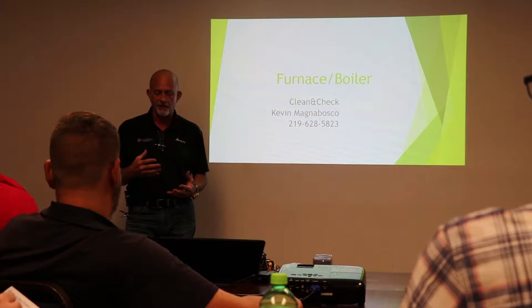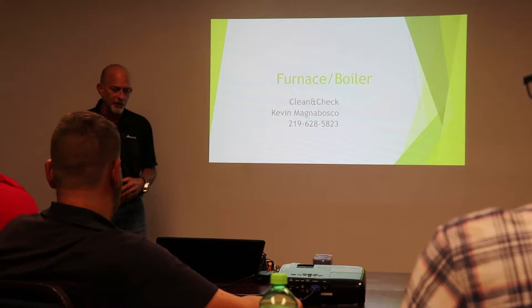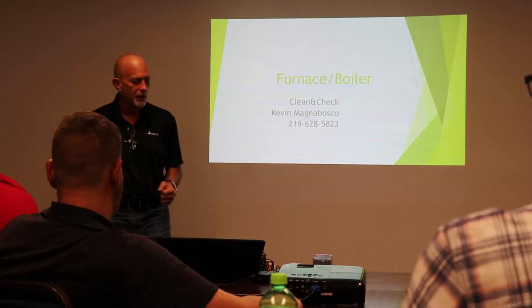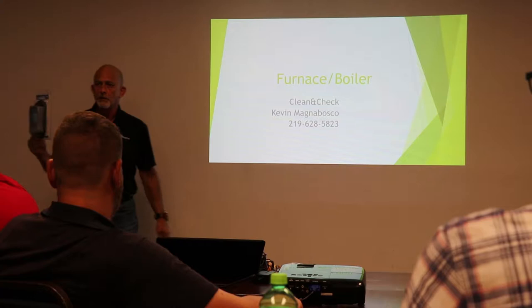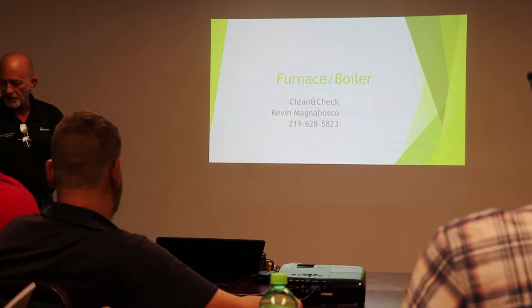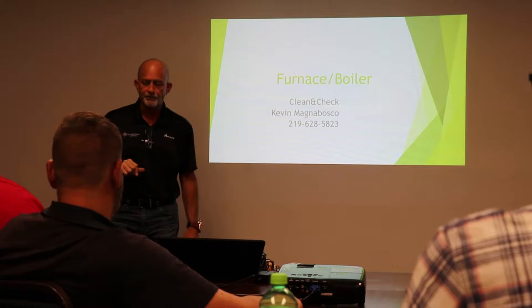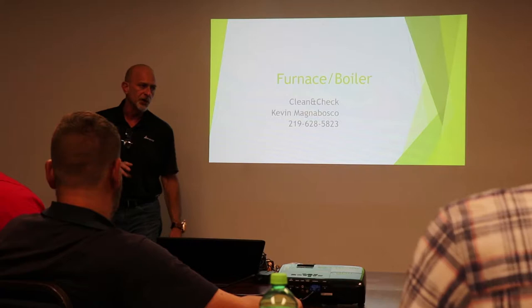So you knock on the door, let them know you're there, explain we're checking the entire system. We can run out to the outdoor unit in the middle of wintertime, and we can ohm out the compressor. Does anybody in the room have a megohmmeter? Nobody in this room. I'll pass this around so you can take a look at this. Very simple tool. We're going to open up our outdoor unit, pull off our connector to compressor. We're going to check each winding, common to start, common to run. Check them to ground.